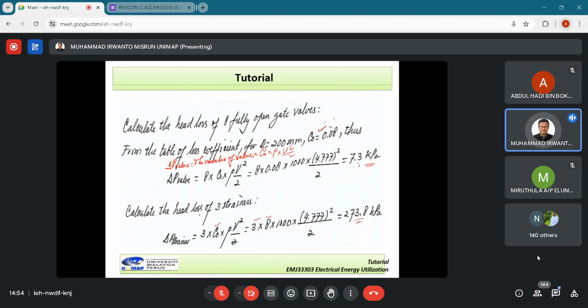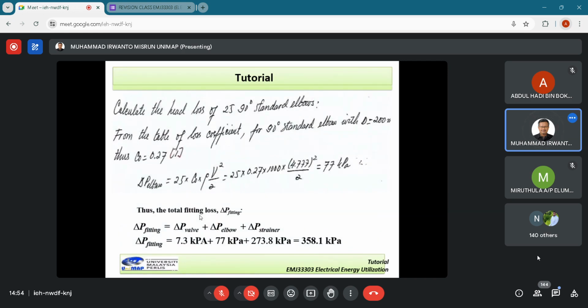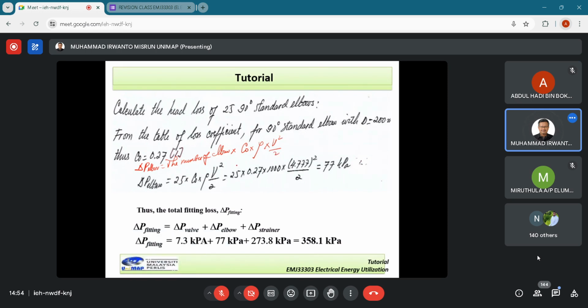Last, we want to find the losses for the elbow. The general formula is the same: delta P elbow is given by the number of elbows multiply CO multiply rho multiply V power 2 over 2. Here CO is the coefficient loss for the elbow, based on the type of elbow.